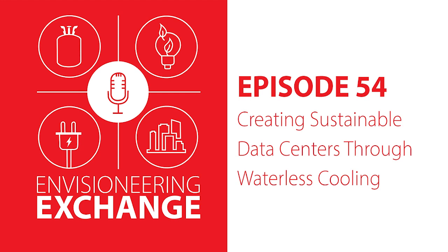It used to be when you designed a data center, your big focus was on the fiber, and then your big focus was on the power, and do I have a reliable power grid, and in some cases, do I want two utility feeds? If you're using water to cool the data center, and especially at the densities that we're talking about, if you lose water, that can actually be more dangerous for you than losing power, because your servers could still be on and they won't just shut off, they'll melt, and you're actually creating equipment damage in that case of losing water.